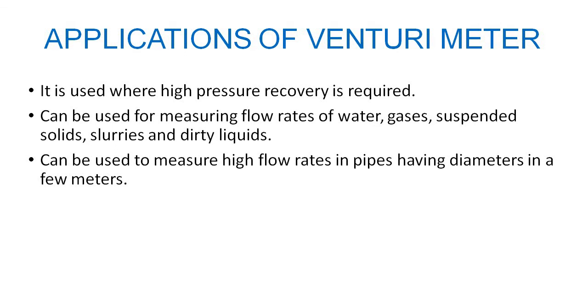Applications of the Venturi meter. It is used where high pressure recovery is required. It can be used for measuring the flow rate of water, gas, suspended solids, slurry, oil, as well as dirty liquid. It can be used where dirty liquids and slurry cannot be measured by the orifice plate. It can be used to measure high flow rate in pipes having large diameter. Thank you.